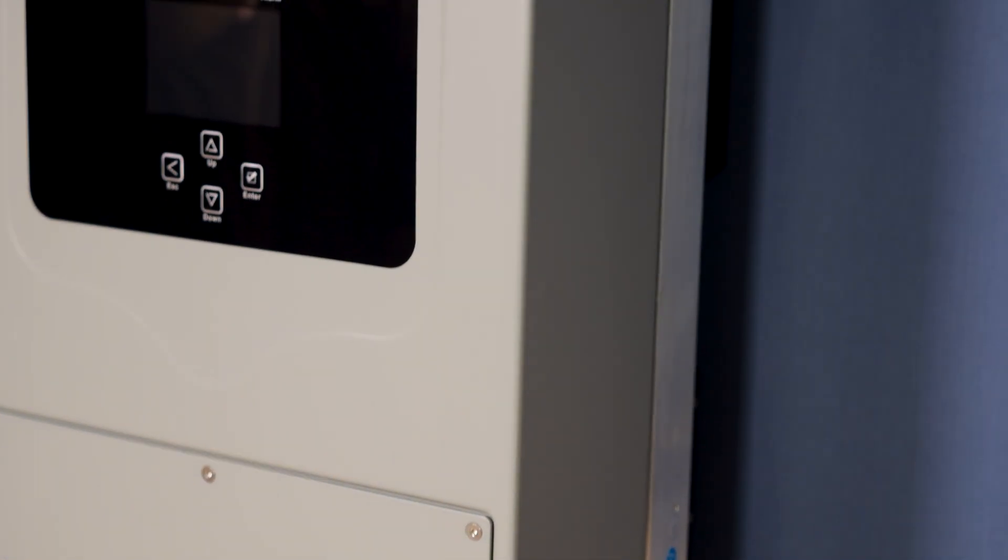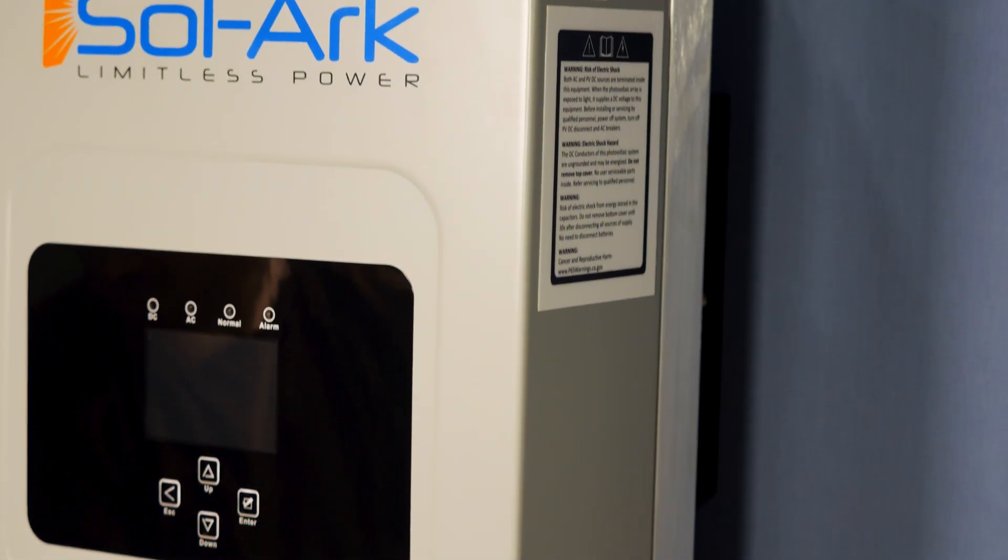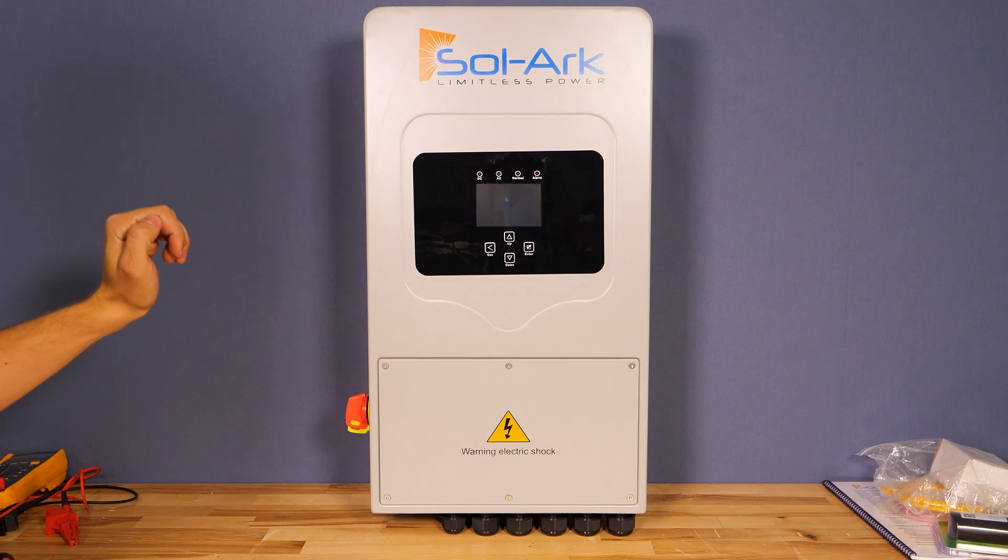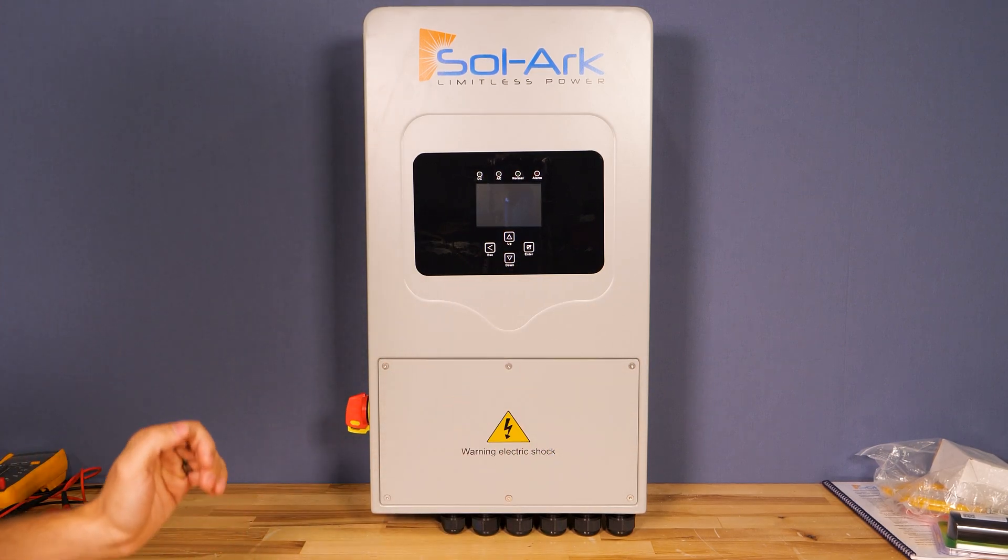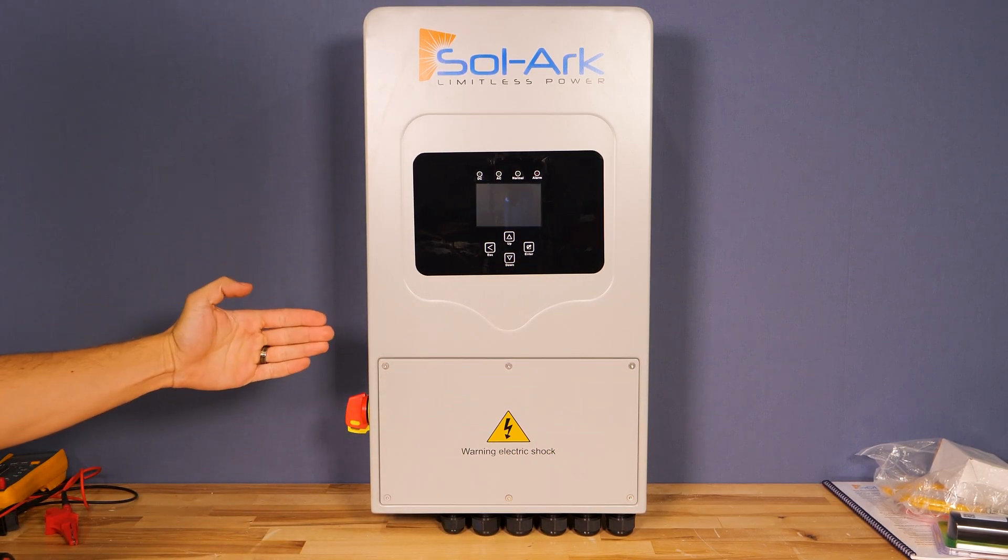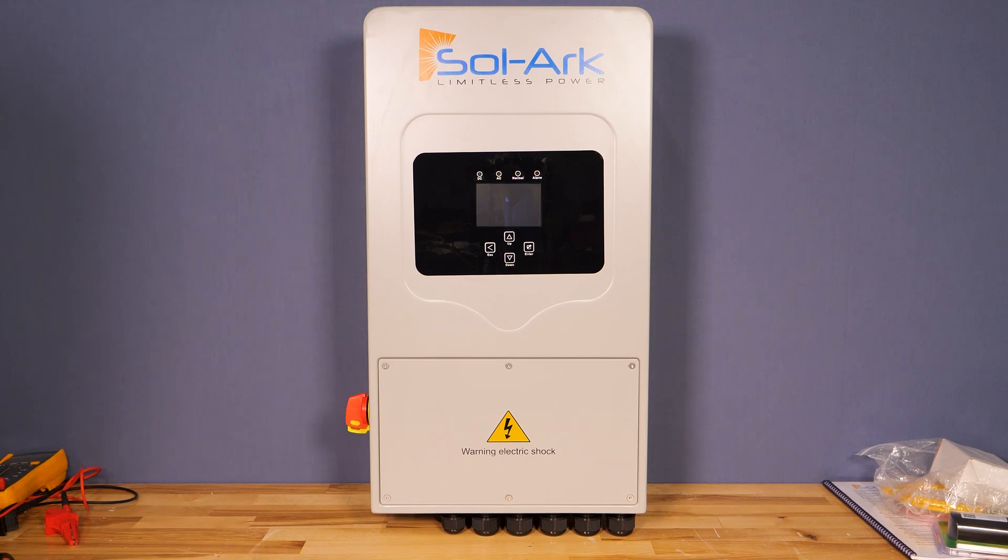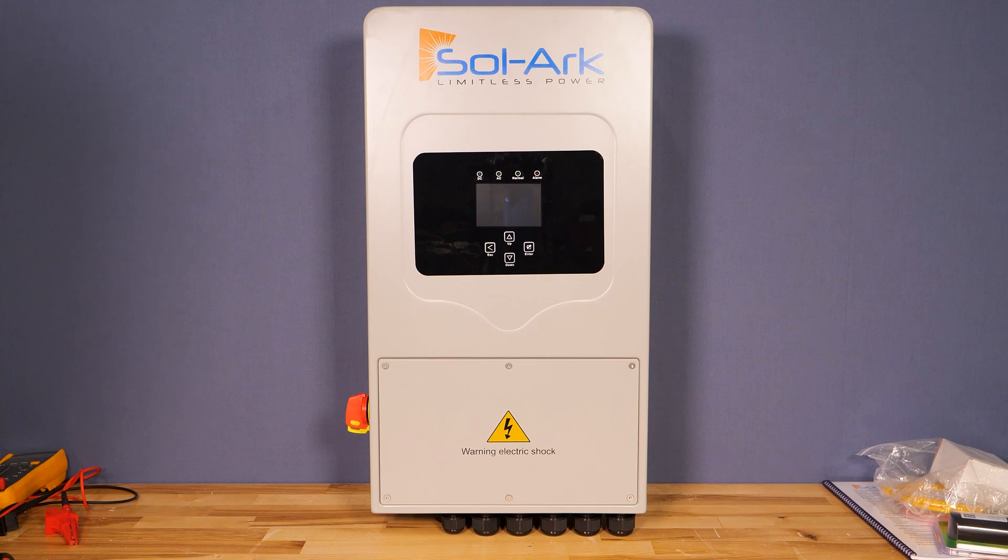This inverter is NEMA 3R outdoor rated so it can be installed in wet environments. It is 23 and a half inches tall, 13 inches wide, and 9 and one-quarter inches deep coming off the wall. It's rated at 4.8 kilowatts continuous at 120 volts, however at 240 volt single phase it can output 8 kilowatts.